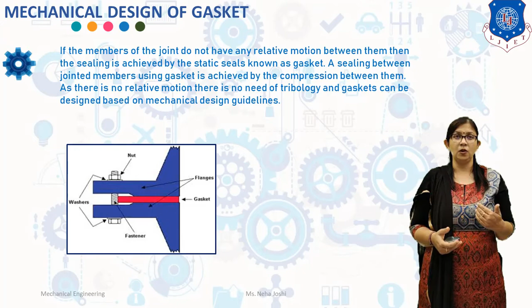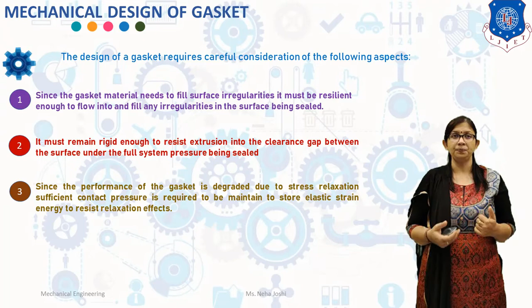Now, design of the gasket requires careful consideration of the following aspects. The gasket material needs to fill surface irregularities. It must be resilient enough to flow into and fill any irregularities in the surface being sealed. It must remain rigid enough to resist extrusion into the clearance gap between the surfaces under the full system pressure being sealed. Next, since the performance of the gasket is degraded due to stress relaxation, sufficient contact pressure is required to be maintained to store elastic strain energy to resist relaxation effects.